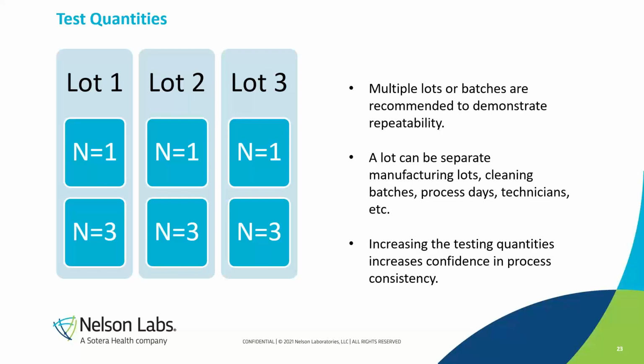More often, that might be 30 plus devices per device type and per test. So it can be pretty high. And I have seen that done. I have seen that included in cleaning validation plans. More often than not, I see three devices, due to the burdensome nature of acquiring that many devices. So most often I see 3 lots with 1 device per lot to produce 3 data points per test method and per device grouping. I have seen a bit of a push lately to increase that on higher risk devices like implants.